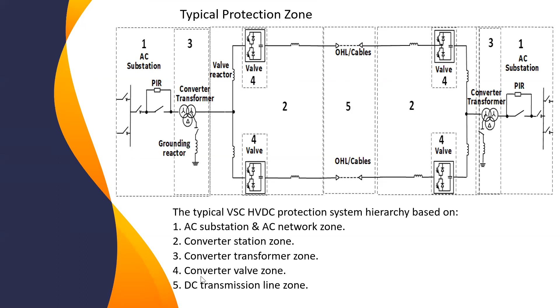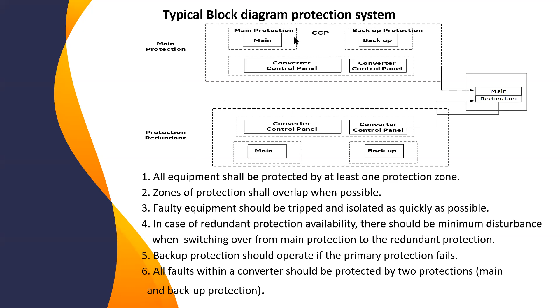This is only typical. So in terms of block diagram and protection, protection in VSC is quite sophisticated. In main protection, we have equipment that shall be protected by at least one protection zone, and then zone protections overlap each other, and faulty equipment should be tripped and isolated as quickly as possible. In case of redundancy, the function will be the same as main protection. In case of redundancy, there should be minimum disturbance time when we switch from main protection to redundant protection. And all faults within converter station should be protected by 2 protections. We call it main and backup. Every time we have main and backup.